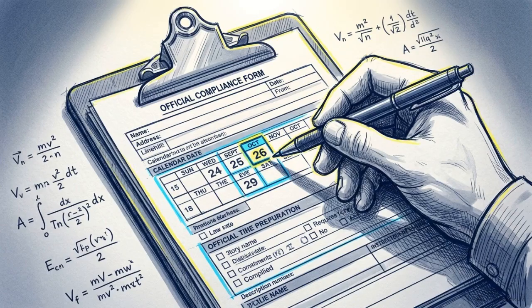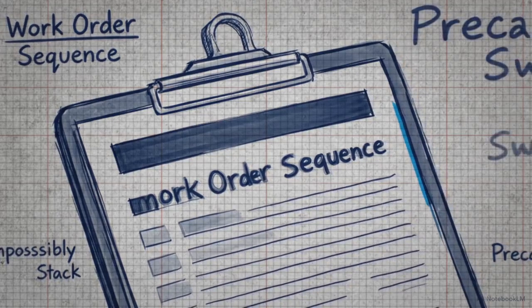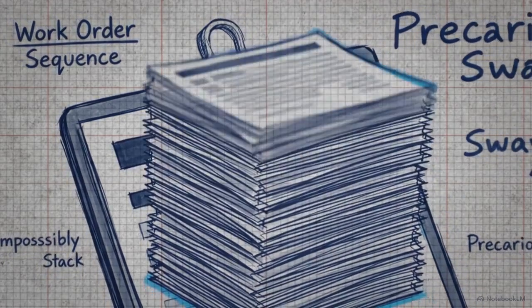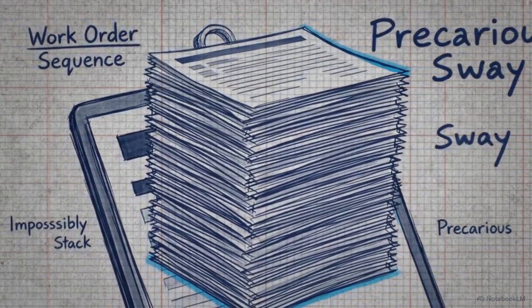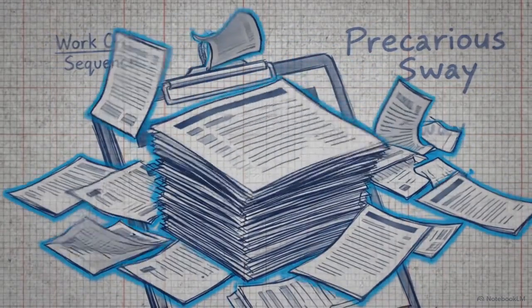Fixed schedules are built for calendar-driven compliance audits, where dates are legally binding. Floating schedules are built for unpredictable, usage-heavy maintenance, where you must prevent work orders from overlapping and stacking up on the same asset. Selecting the wrong scheduling logic is the primary reason automated maintenance plans either stack up impossible execution backlogs or drift out of legal compliance.